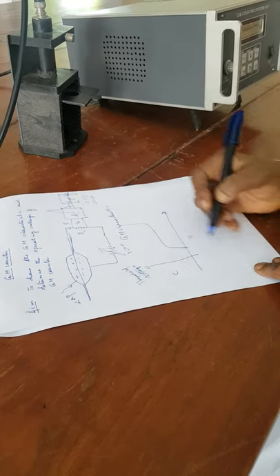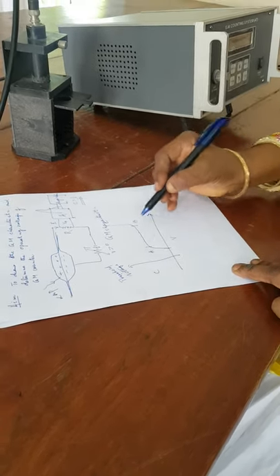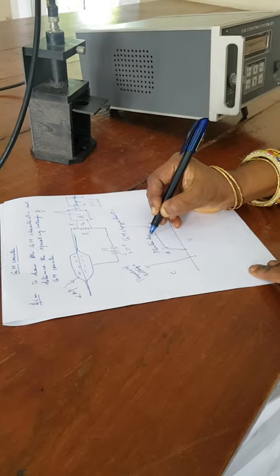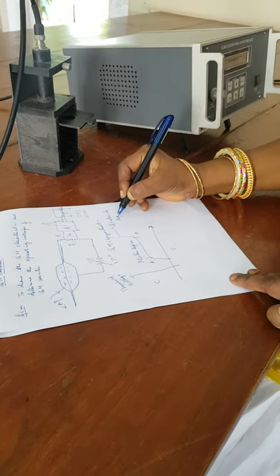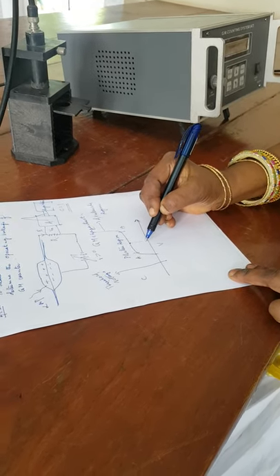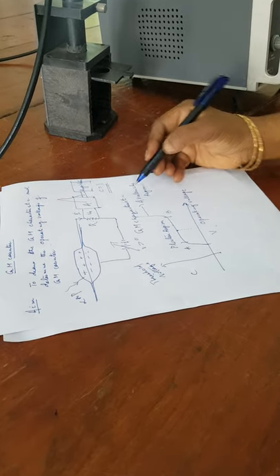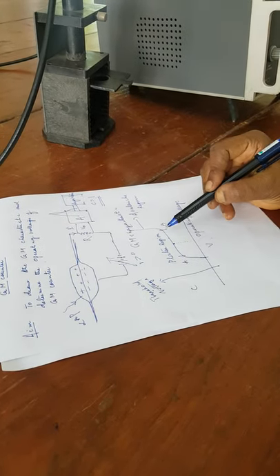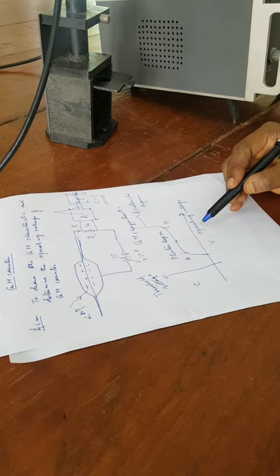In the GM characteristic, we see two specific regions: A-B and B-C. A-B is called the plateau region and B-C is called the avalanche region. The range of voltage at which the counts remain almost constant is called the plateau region.